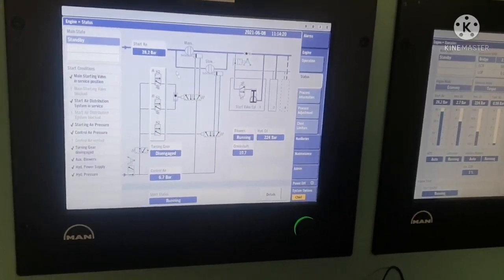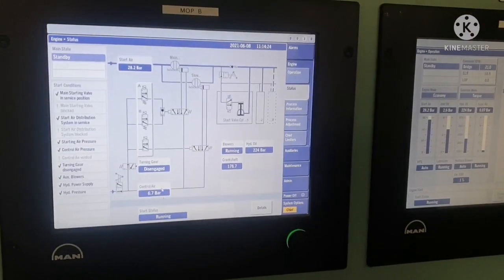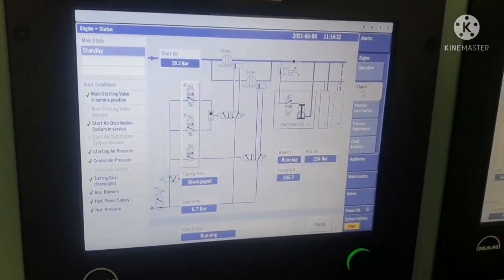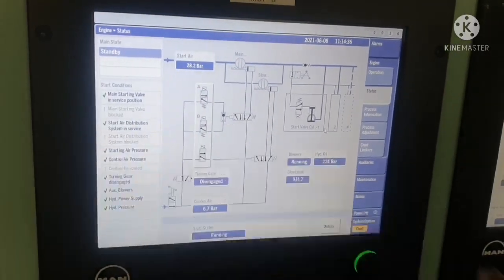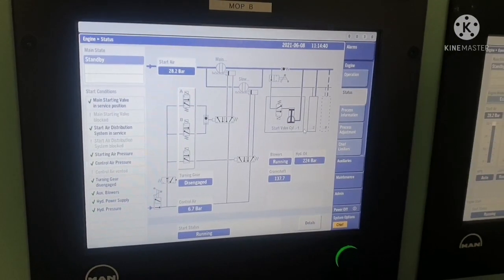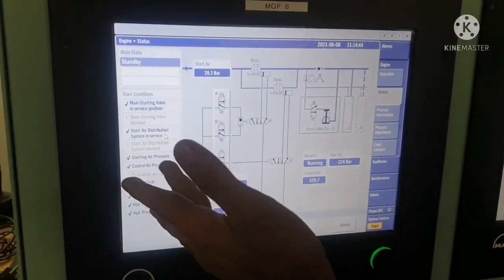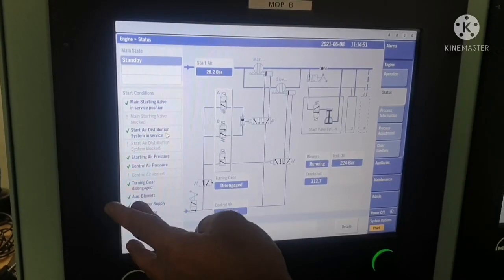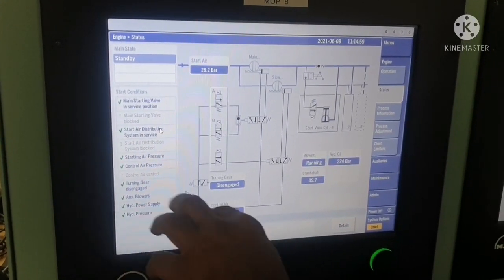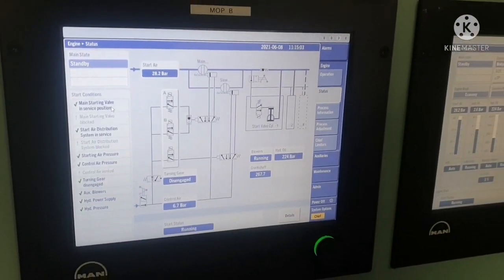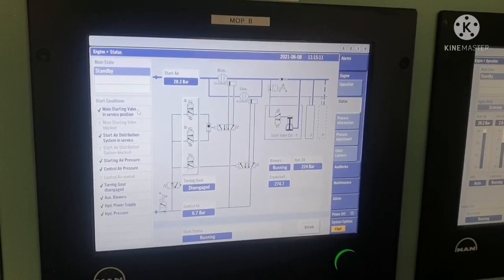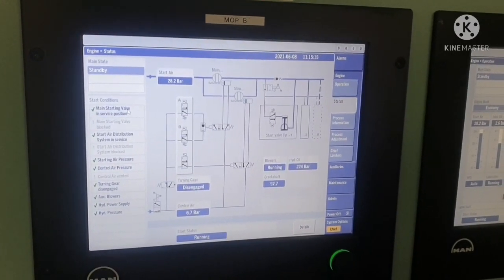Now the main engine is running. If you find everything in green, that means your unit is perfectly alright. If you find anything in red color, that means there is some problem in that system. For example, if the turning gear disengaged indicator is red, that means the turning gear has a problem or is not disengaged properly. If control air pressure is shown in red, that means the pressure is low. Any abnormality will show in red color; everything normal will show in green.